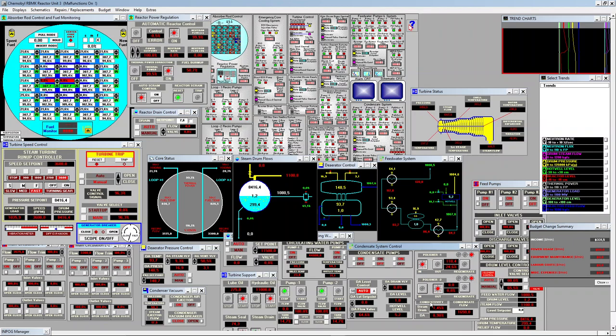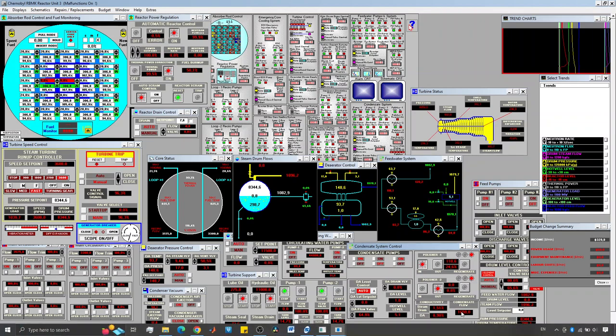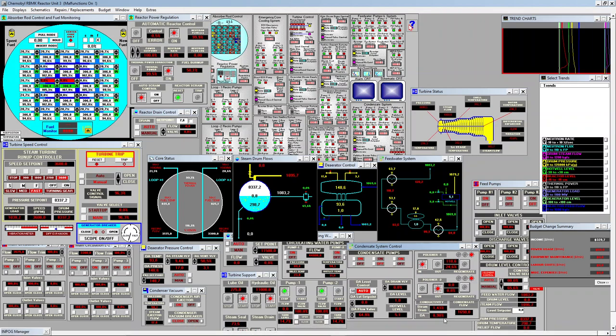So when the conductivity indicator here in the drum and in the deaerator goes high, you need to do something about the polishers. For the moment, the conductivity is just 1% and 0.9%, so within normal operation, water is clean. Conductivity indicates how many salts are dissolved in the water, so low conductivity means clean water. If we have high conductivity, we will end up with corrosion of the different parts of this nuclear power plant. Later, I will explain how to regenerate the polishers when they get too dirty.